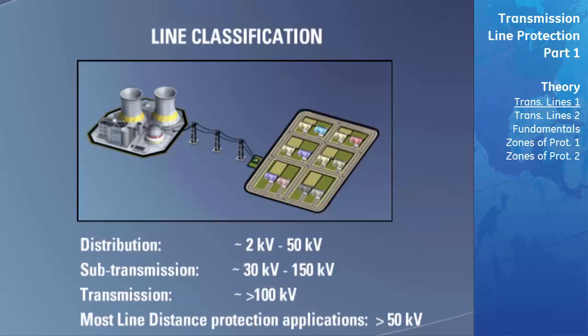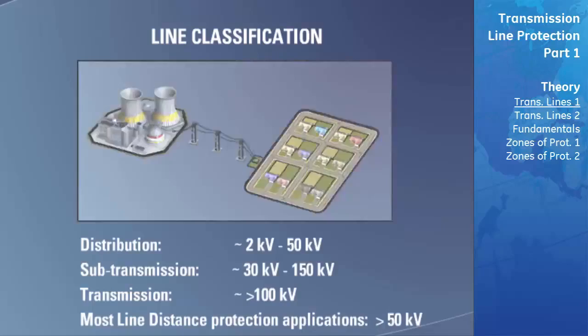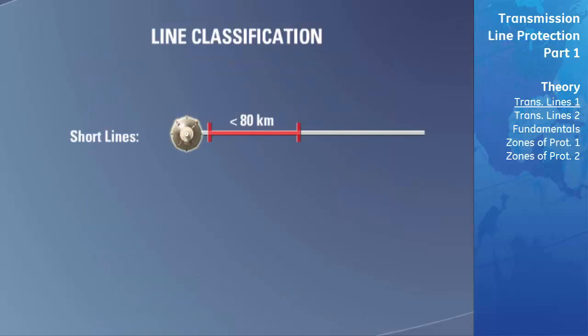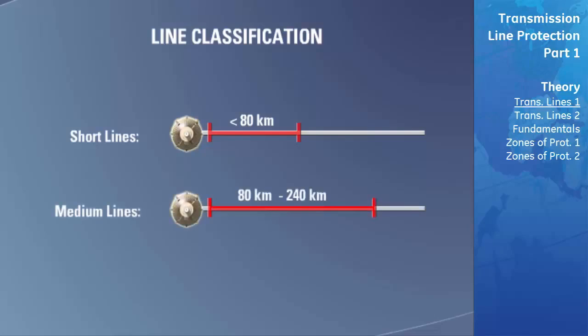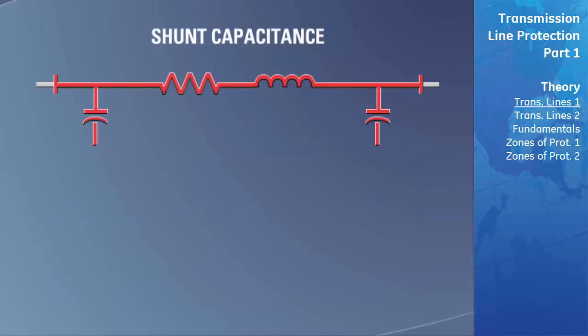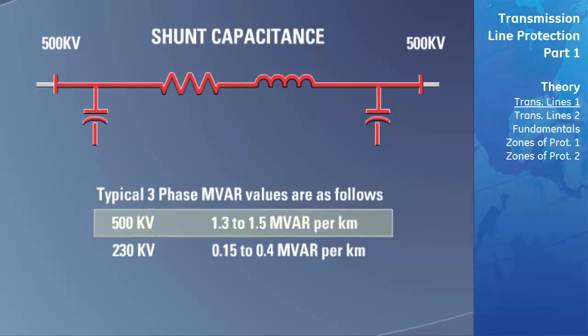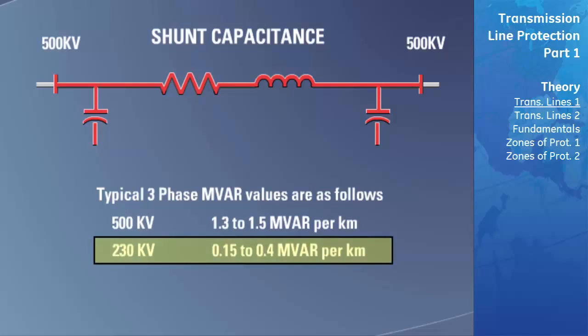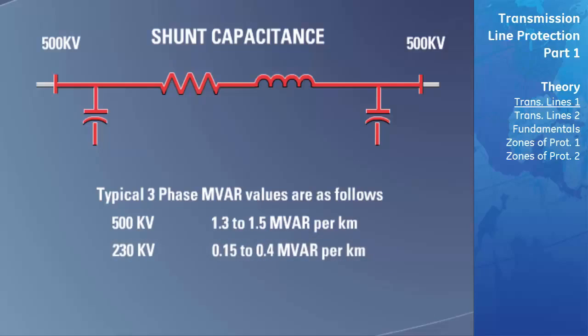The lengths of transmission lines have been classified into three categories. Short transmission lines are less than 80 kilometers in length. Medium transmission lines are roughly between 80 and 240 kilometers. Long transmission lines are greater than 240 kilometers in length. Typical three-phase MVAR values are 1.3 to 1.5 megavars per kilometer for 500 kilovolt lines and 0.15 to 0.4 megavars per kilometer for 230 kilovolt lines.